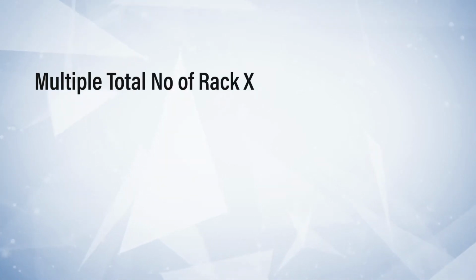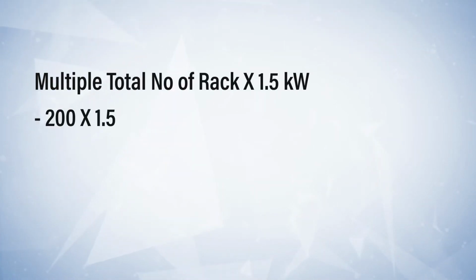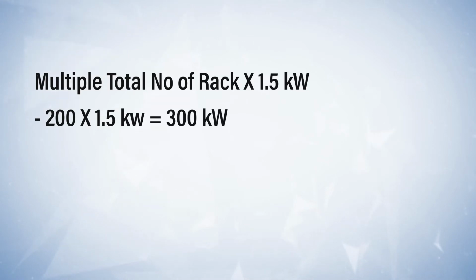Now we multiply with the total number of racks in the data center. We get 1.5 kilowatts per rack into 200 racks. That is a total 300 kilowatt load. Right, keep in mind this is just critical load. We need to calculate even further. Wait, this is not over yet.